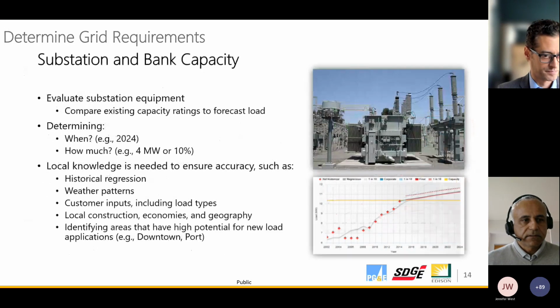Determining grid requirements at the substation and bank capacity level, we're evaluating our substation equipment, comparing the existing capacity versus the forecasted load. Then we determine when that need occurs - what year, and how much that load is, whether it's megawatts or percent.